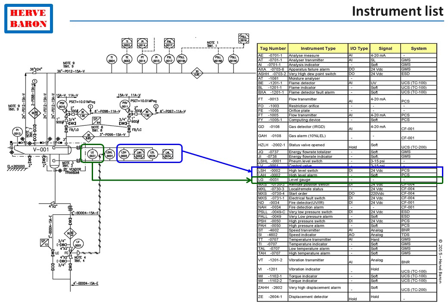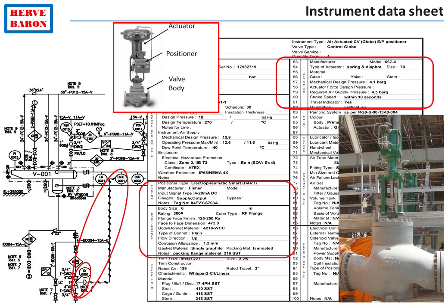For the other instruments, the process information is available on the heat and mass balance. The process data sheet of a control valve, for instance, shows the functional requirements — the operating range and extreme operating cases — as well as the maximum differential pressure for sizing the actuator and the fail-safe position. The instrumentation discipline complements this process information with mechanical, electrical and instrumentation information, and produces the instrument data sheet.